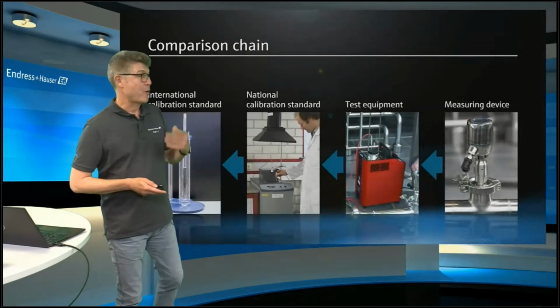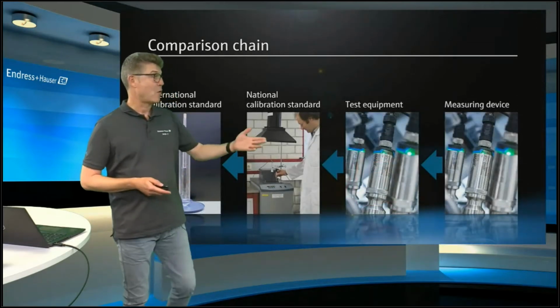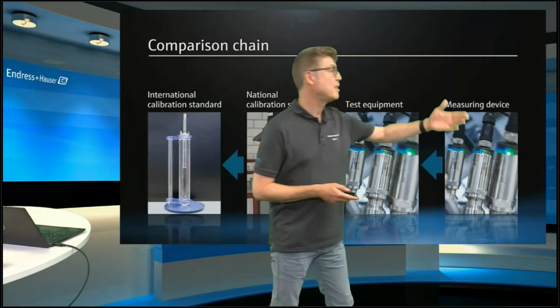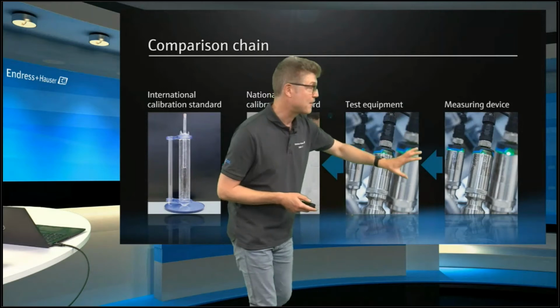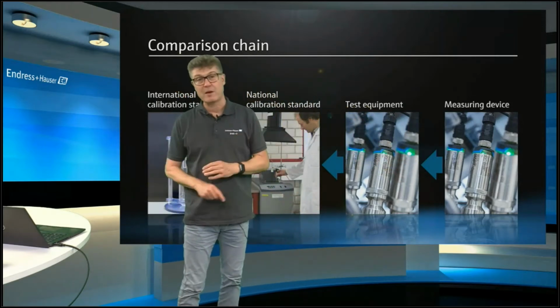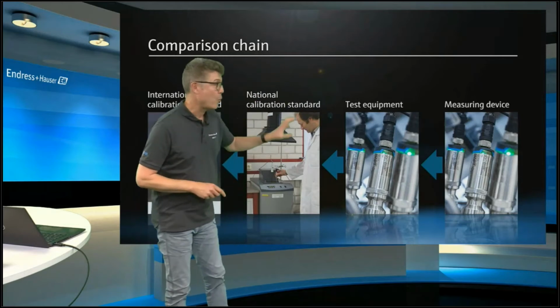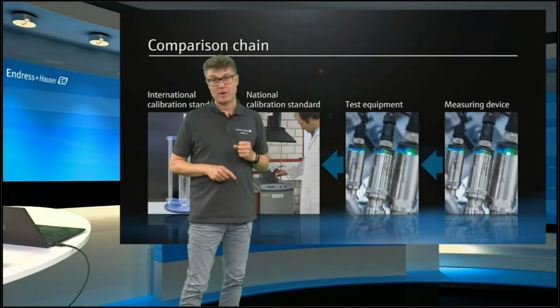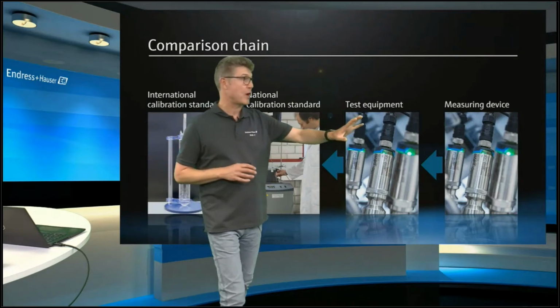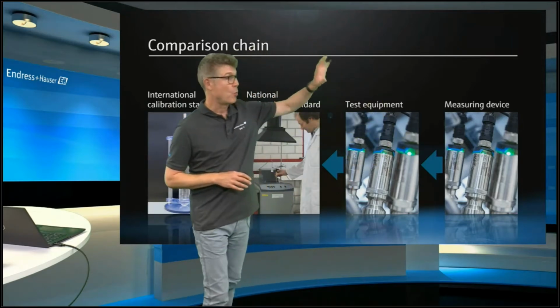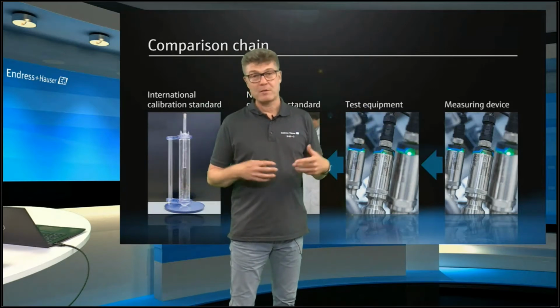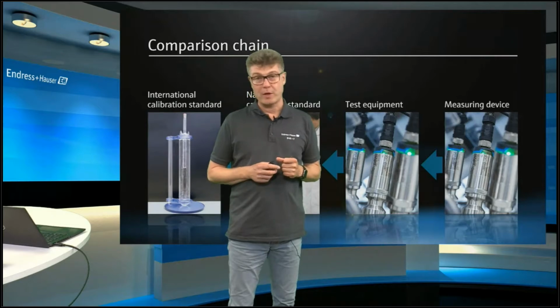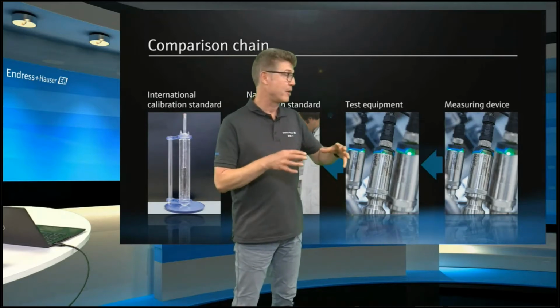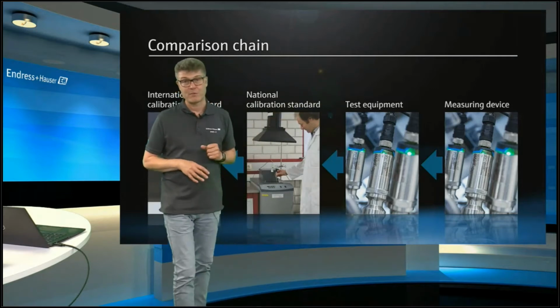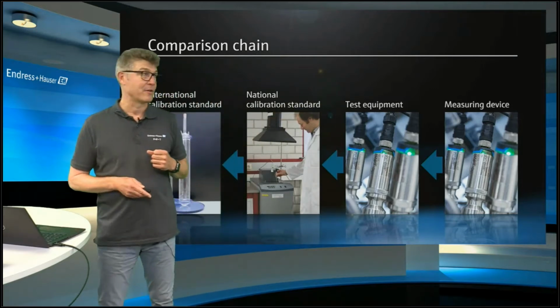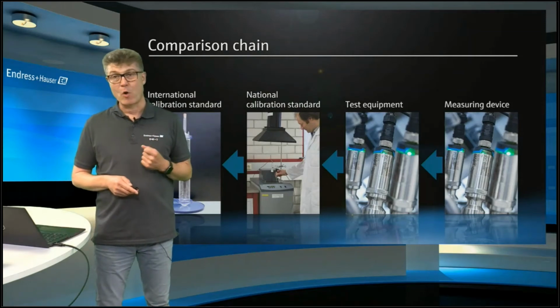So the comparison chain is now that the measuring device includes the test equipment, and this is still produced here in our production site, where we have a National Standard Calibration Institute. And so the traceability chain is still closed, because we do the original measurement of where the Curie temperature of this individual design, the individual instrument, is, and then it is fixed forever. This is the story behind this long-time stability.